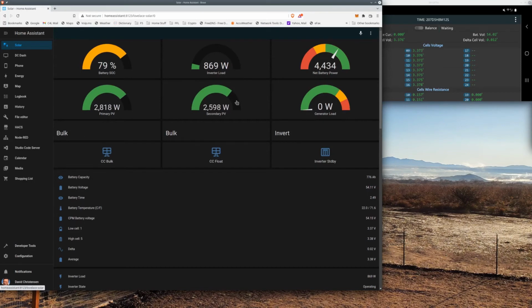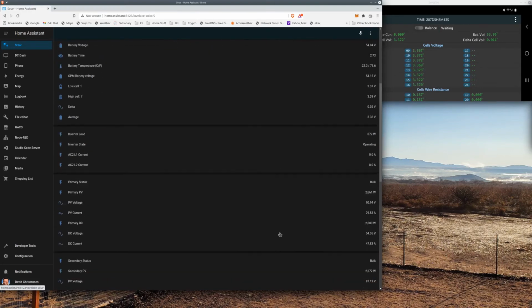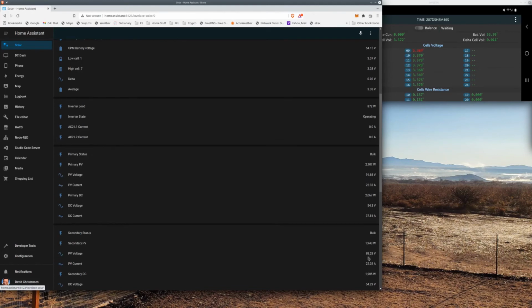Now, what you may notice if you did some calculations - these together, the two arrays and the inverter load, do not add up to this net battery power. What I'm showing here is the watts coming in directly from solar. If you've run solar at all, you'll notice there are losses between watts coming in from panels that get converted or down-cycled to the correct voltage for the batteries, because these are coming in at 90 volts and 88 volts respectively for the primary and secondary.